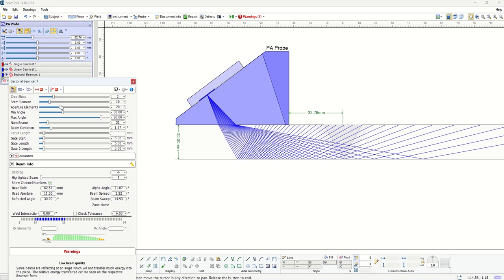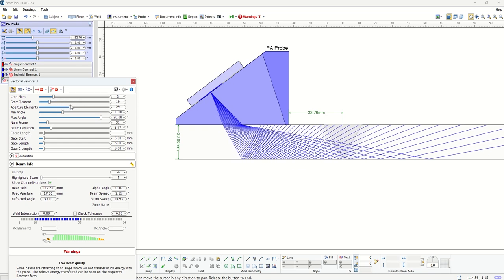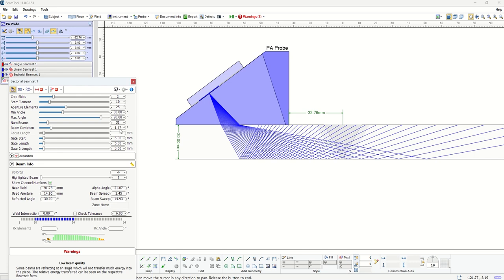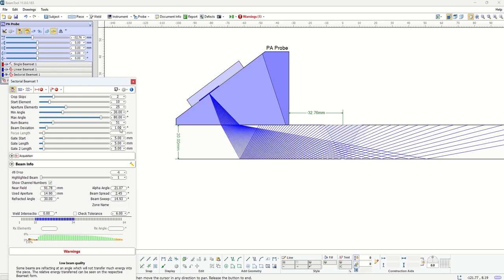Obviously, if you move the starting element or increase the number of elements in the aperture, it will accordingly shift the position of these beams. Since you define your minimum and maximum angles, you can either specify how many beams between the min and max angle you want, or more simply choose what kind of angular deviation you want. For instance here I can say one degree, which means I have 51 beams between 30 and 80, or I can choose 0.5 and that would be creating around 100 or 101 beams between these angles.